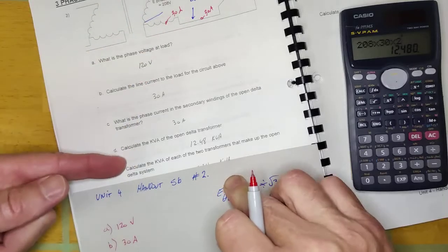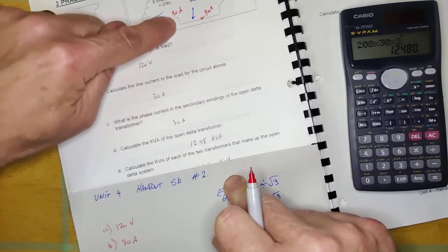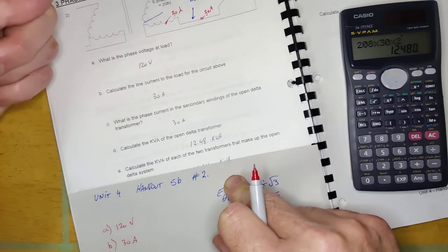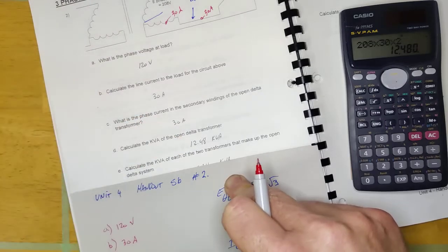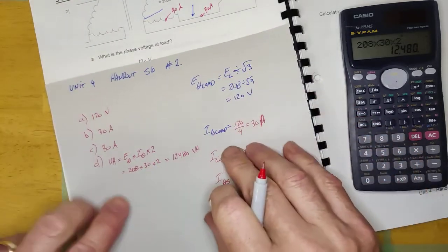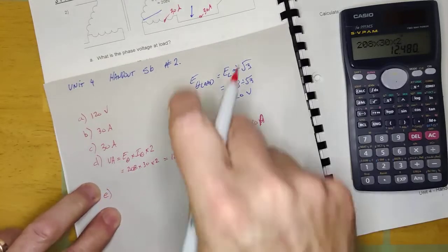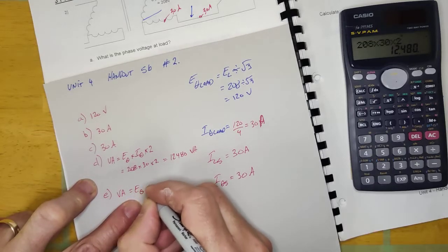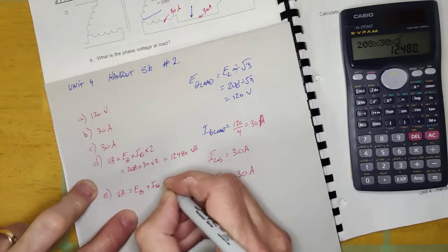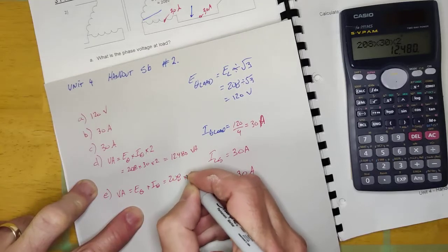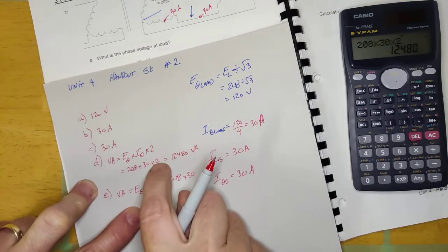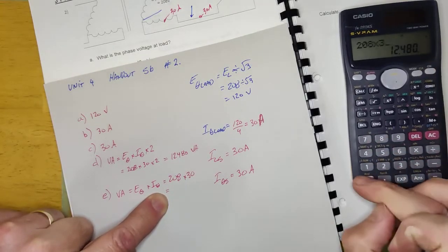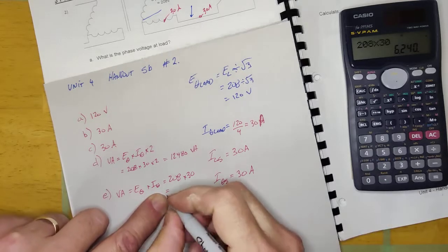Okay, well, there's two ways to do it. You can divide this in half, because this is the VA of the whole thing, and it's made up of two. So I could just take this 12,480 and divide it by 2, or I can calculate the VA of one of the windings, and the VA of one of the windings is going to be E phase times I phase. Okay, and so it's 208 times 30, and it's going to end up being half of that, right? Because we're not doing the times 2.